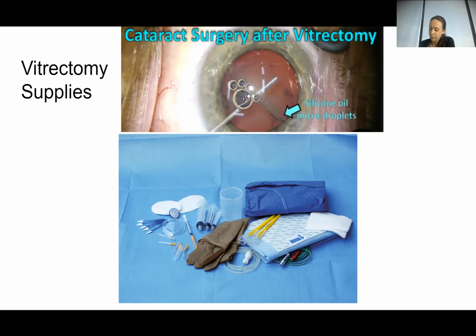And then you can see on your infusion system, one side has the syringe and one side has the infusion. So there's a pump actually pumping this throughout the case. Now, because of that, because it's going to be infusing, look at your practical considerations on the top of 624. So the infusion cannula must be primed and the air bubbles must be removed. This is done as soon as possible.